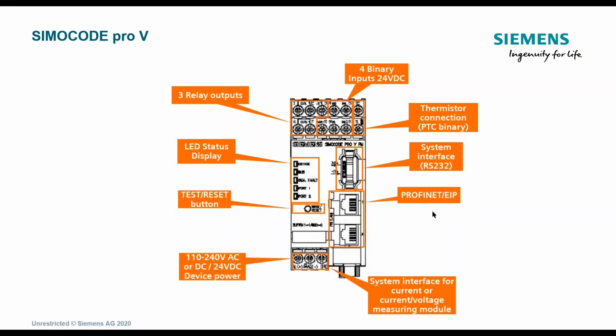Here's the breakdown of the basic unit. Now, when I'm emphasizing basic unit, that terminology is used in the configuration software TIA Portal. So you'll see me say, hey, the basic unit. So the basic unit has 3 relay outputs. Those 3 relay outputs could be for a direct starter, could be for pulling in that coil, and the other 2 outputs could be for maybe doing a lead lag scenario of a compressor or some pump. And the other 2 outputs can be maybe for indicators.